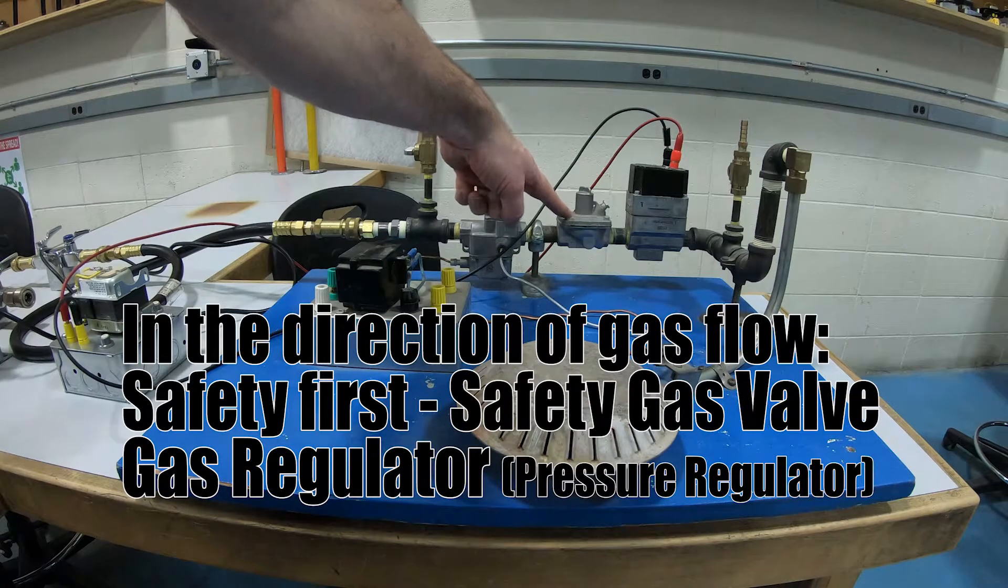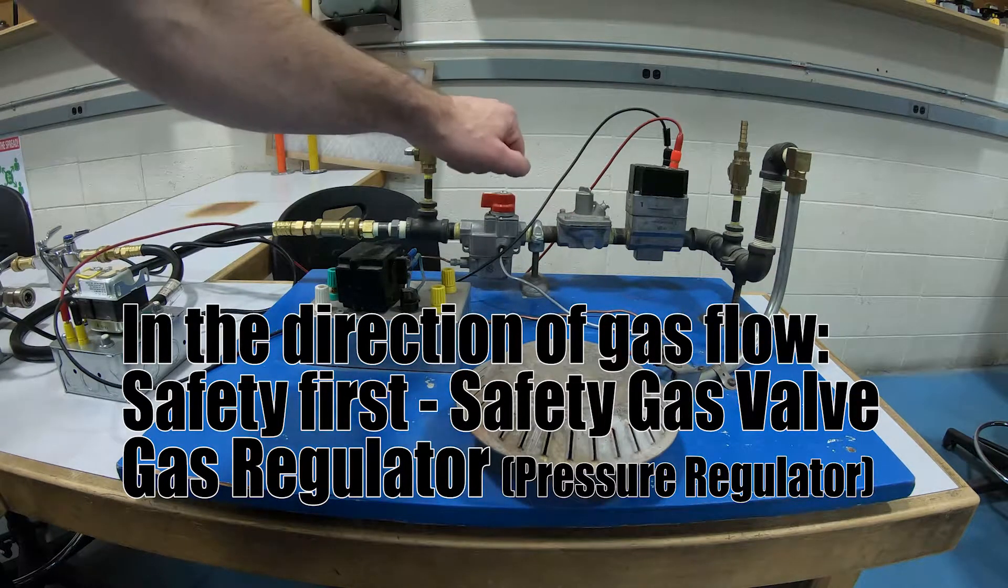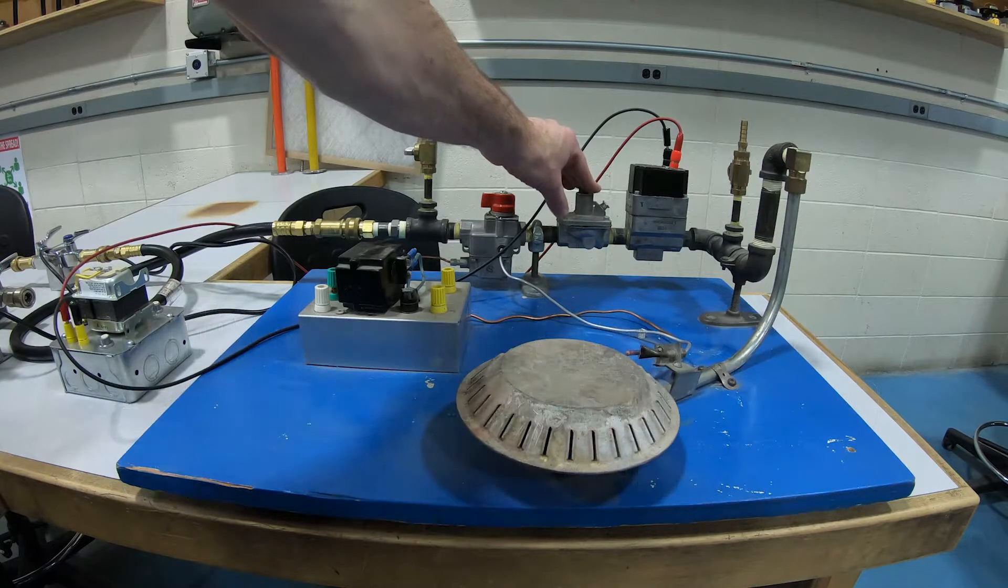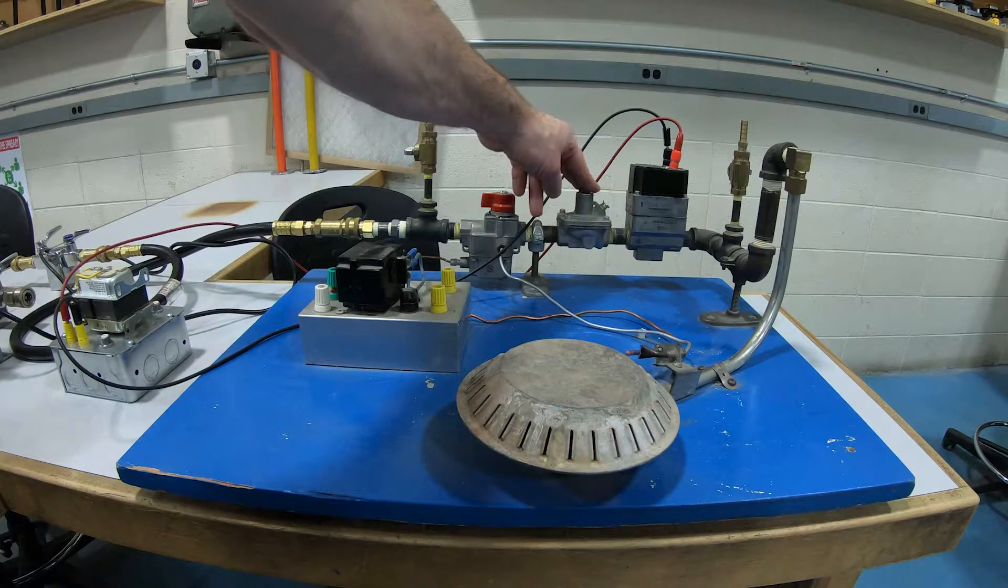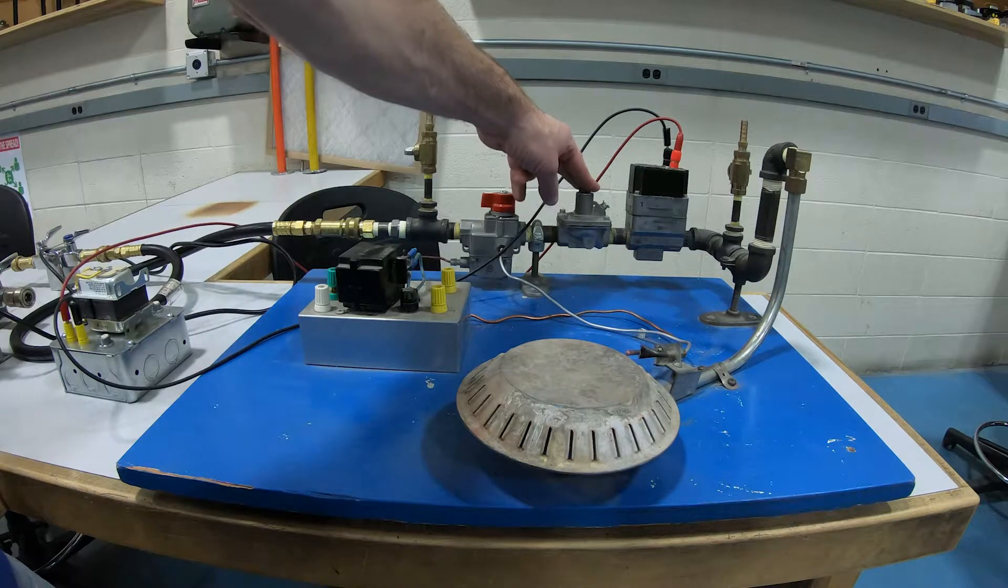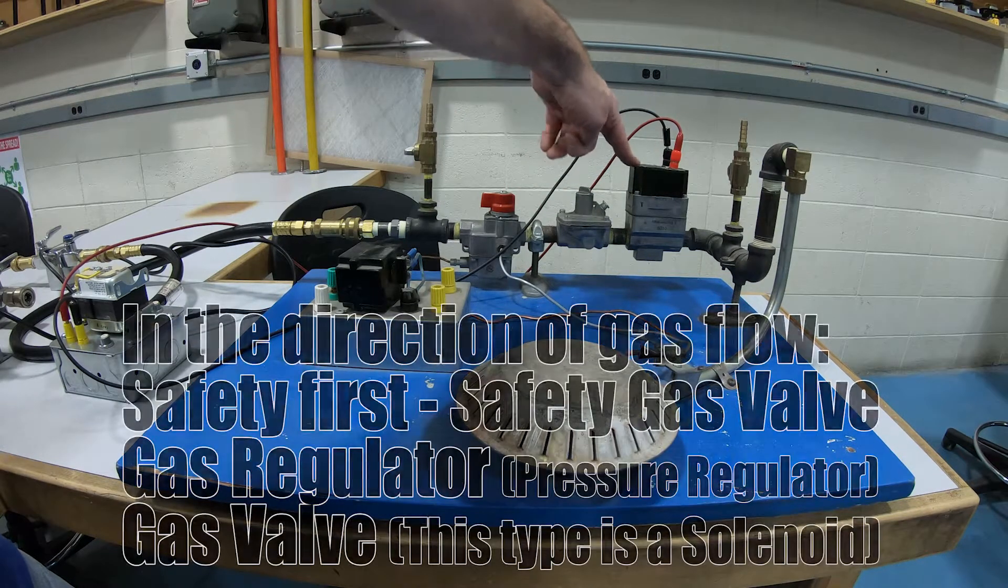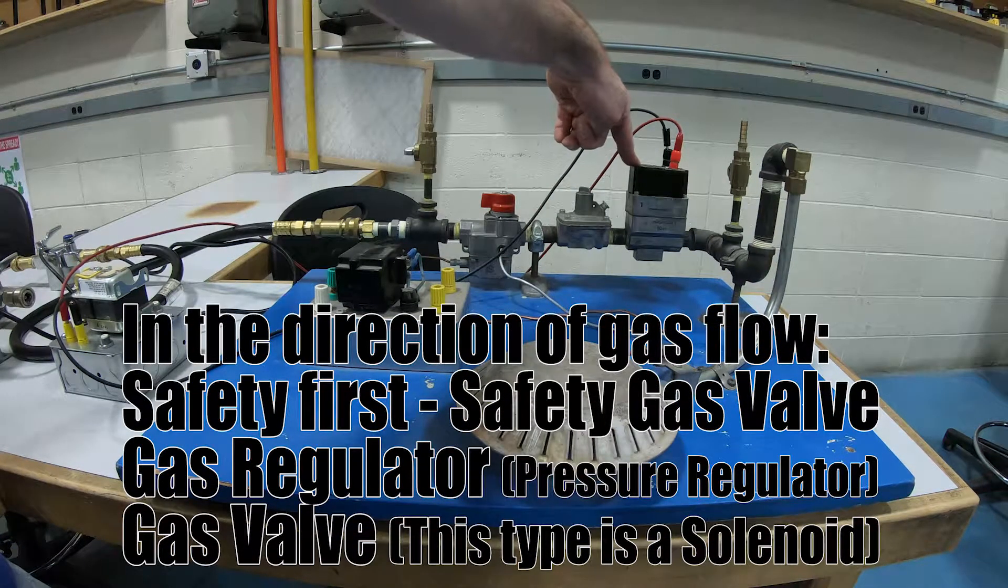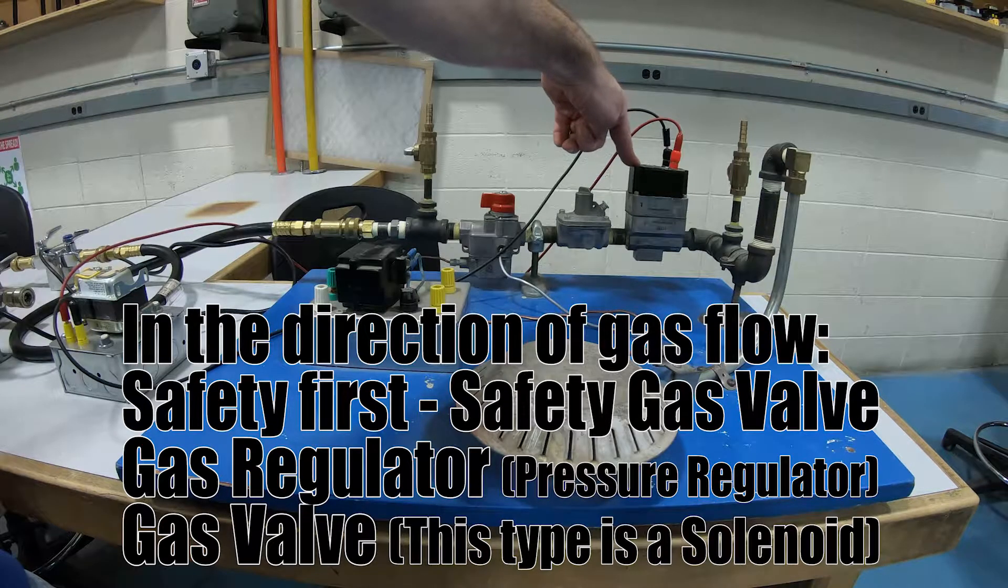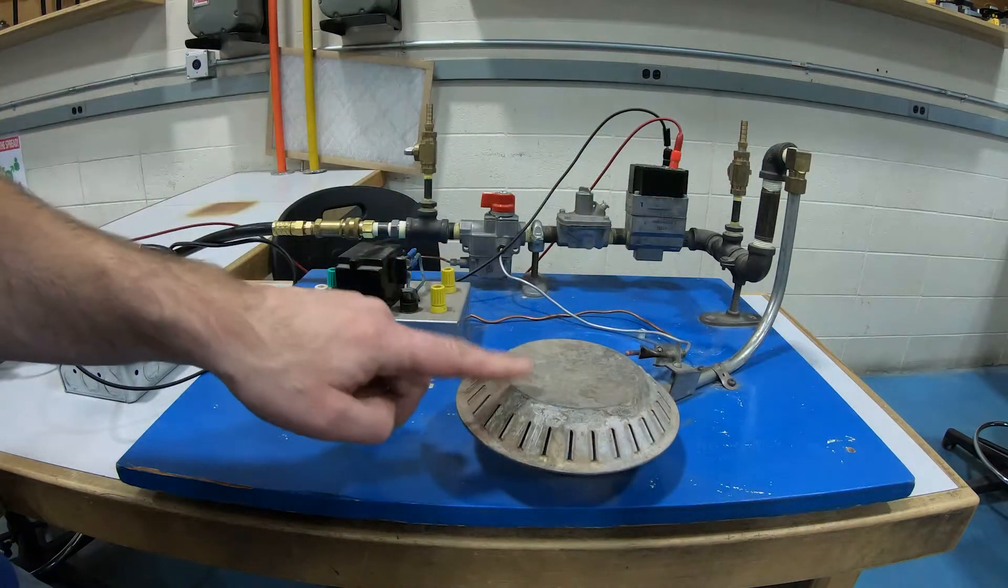The next device is the regulator. The regulator will take the gas pressure down from about seven inches of water column to about 3.5. The next device is controlled by our thermostat. This is a solenoid gas valve and then we just go off to our burner.